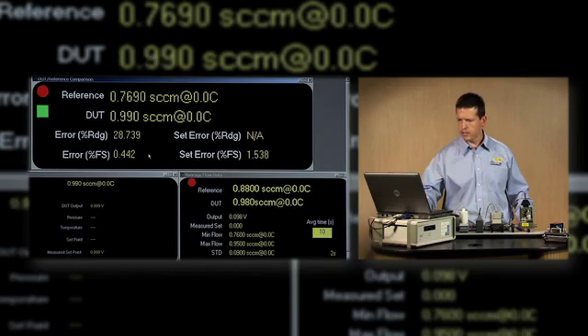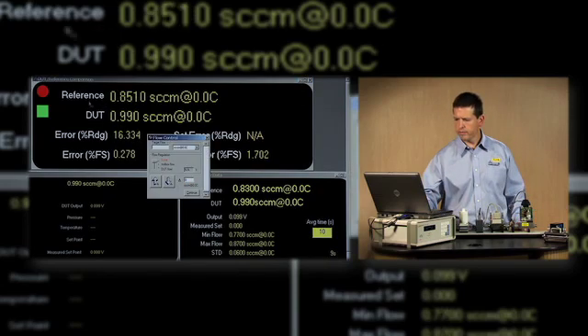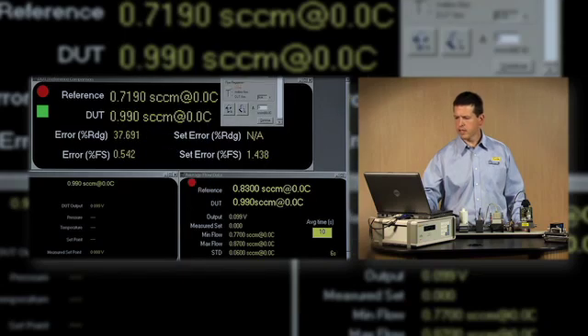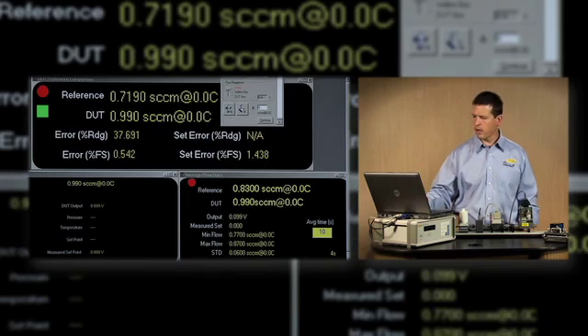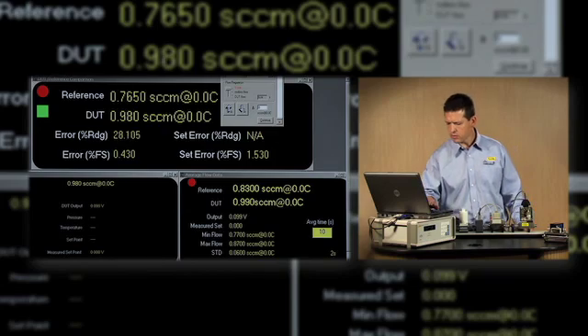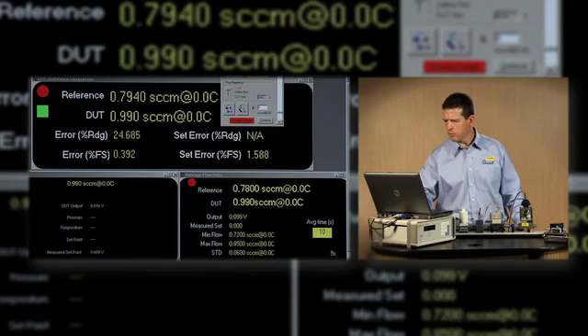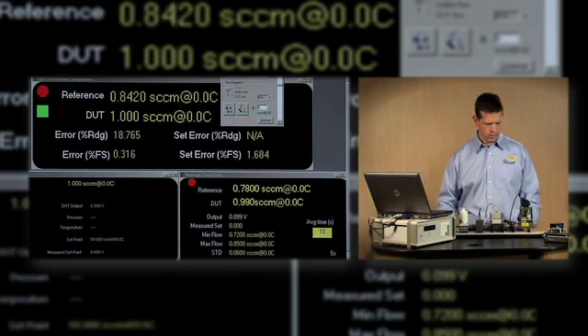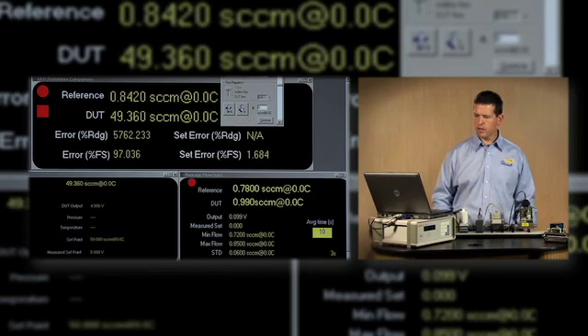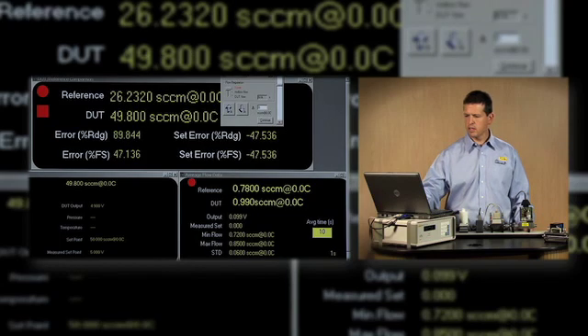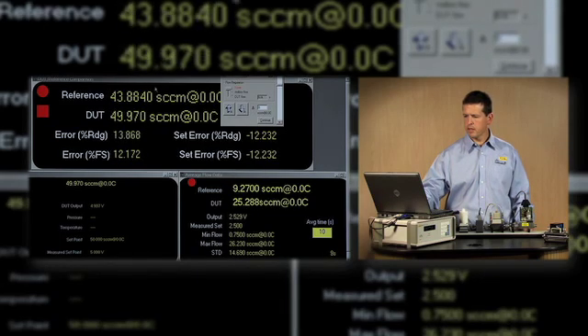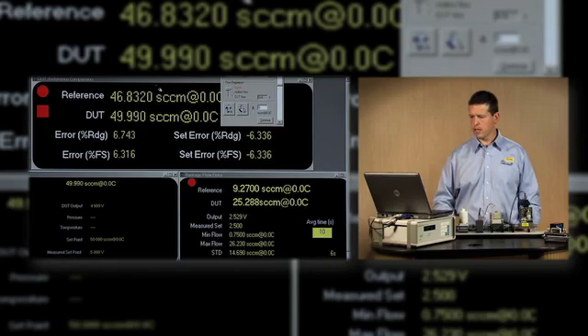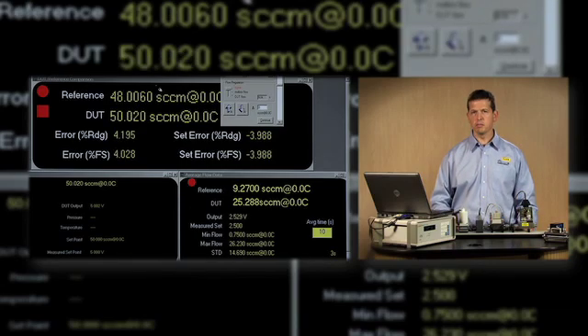So now I can bring up my set flow dialog on the compass window and type in my next point. Now the proper operation of making these adjustments would be to next set the 100% or 50 sccm test point. So I've set my flow. You can see the device under test reading is there. The reference indication is coming up. If I give them a few moments to stable out, we'll be able to make that adjustment as well.